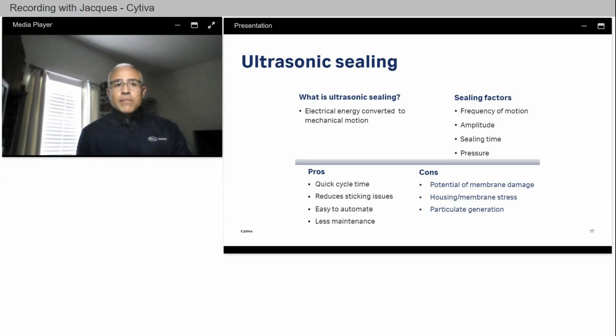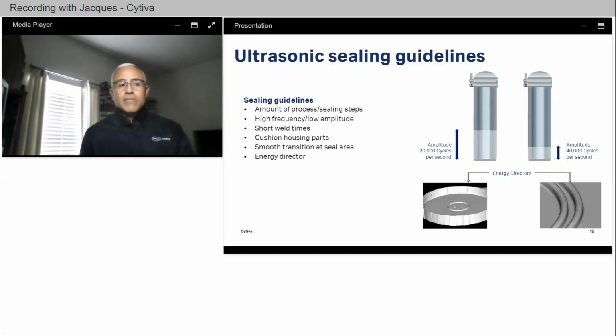However, you should be aware of certain challenges that may be encountered when using an ultrasonic welding method. These include the potential for membrane damage due to the vibration, high stress on the membrane and/or the housing, and particulate generation from these components. So the following general guidelines apply. Experience suggests that reducing the number of process steps minimizes the risk of damaging the membrane during the welding. So use as few process steps as possible.